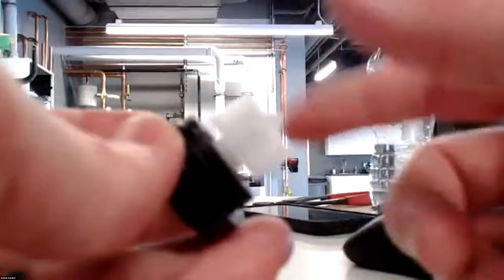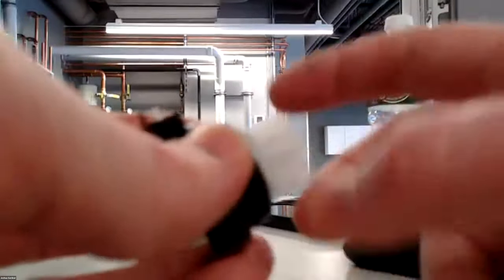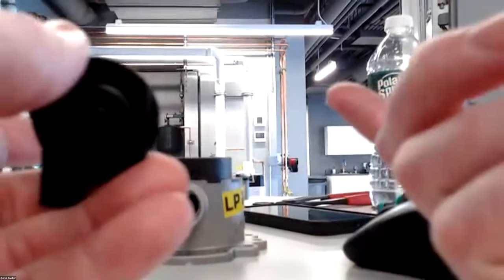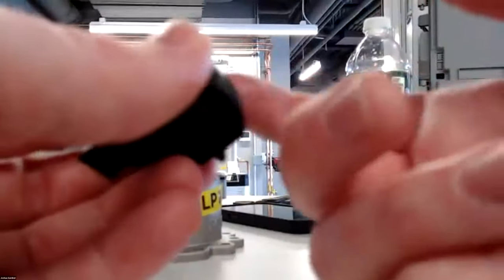So if you're trying to diagnose a no domestic call, this will give you some info as well. One thing to note, I've seen a couple times on the incoming, debris get caught up in here and stick this wheel. So if you do have a new install, you're getting no flow, but you're getting water through it, check and make sure you don't get any debris in there hitting this flow wheel, sticking it up.